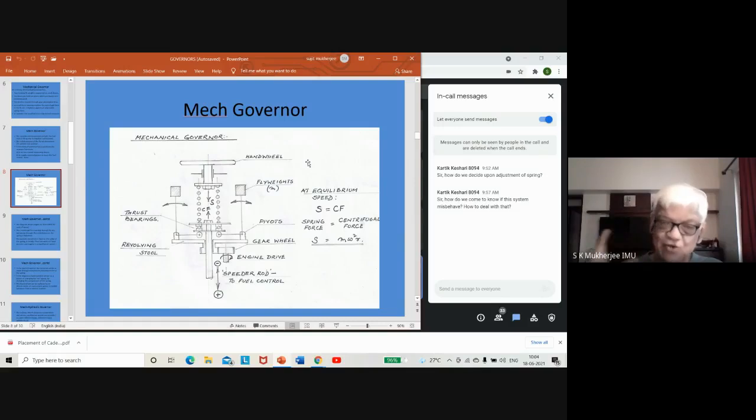So then we used electro cleaner to clean that whole thing. We didn't have any spare. So we cleaned it thoroughly, put it back, and then ensured that the current would come to the governor. And then we started the engine. Lo and behold, it became perfect. To find the problem is about 75 to 90% of the problem. To rectify a problem in the engine room is 5% or 10%. But you need to identify where the problem is. You start your engine and this thing overspeeds.